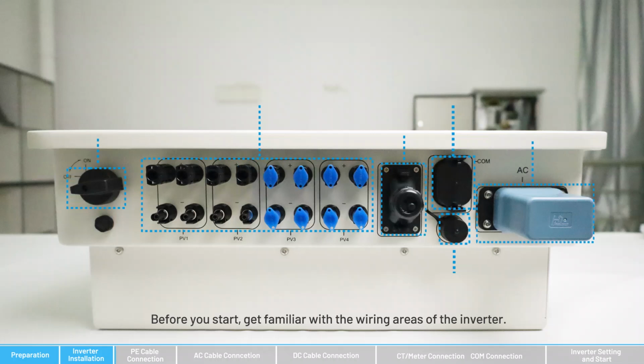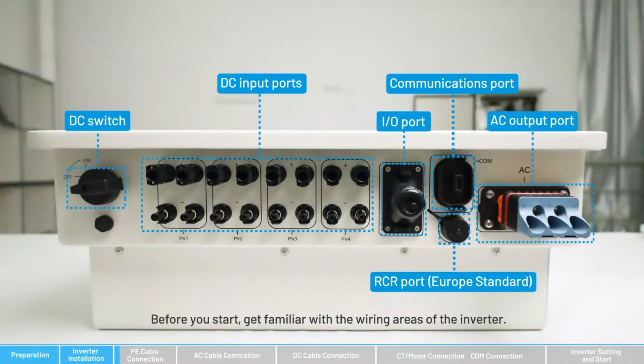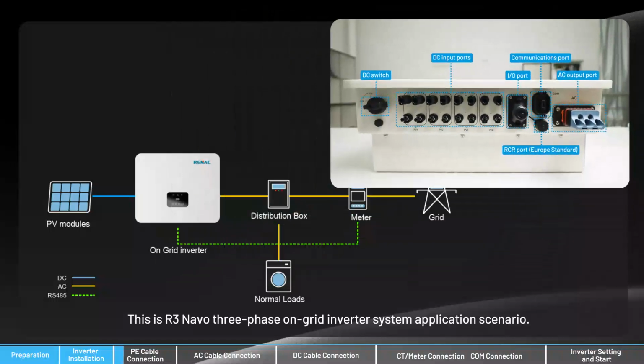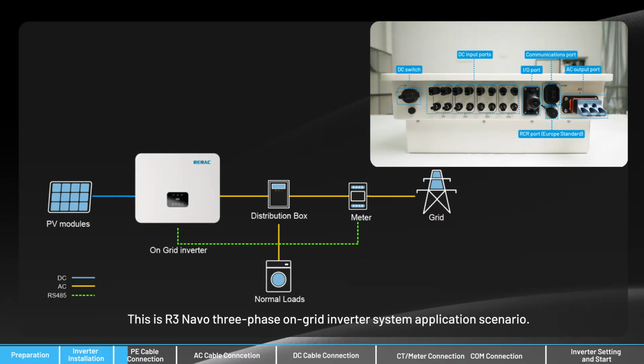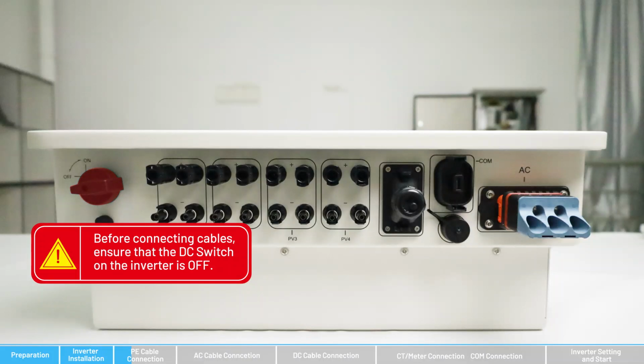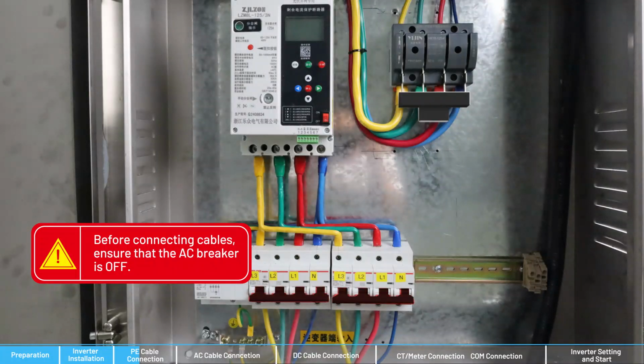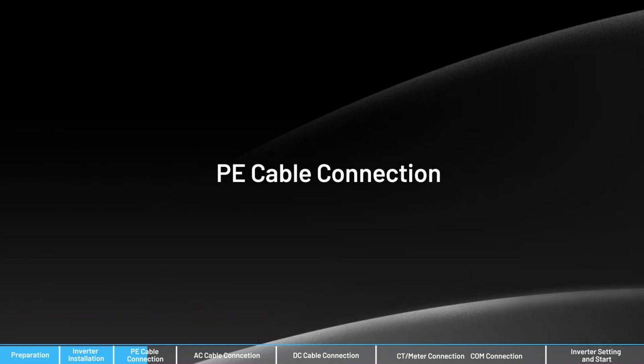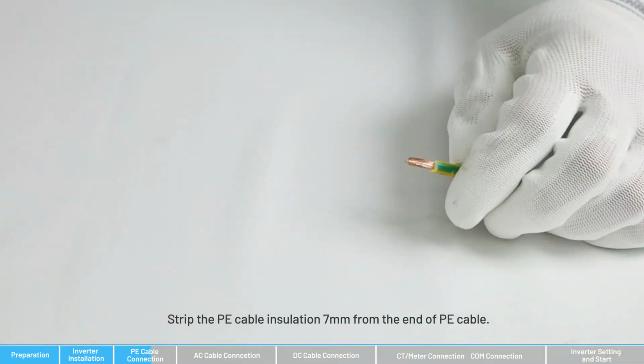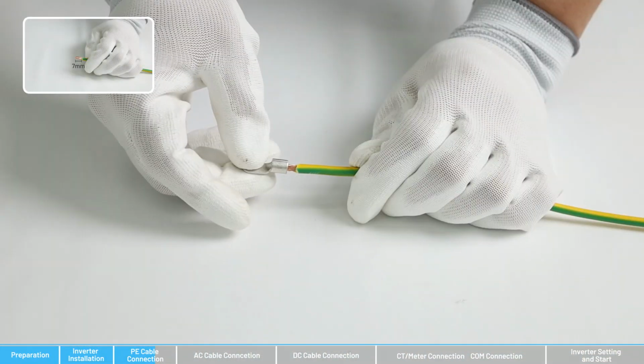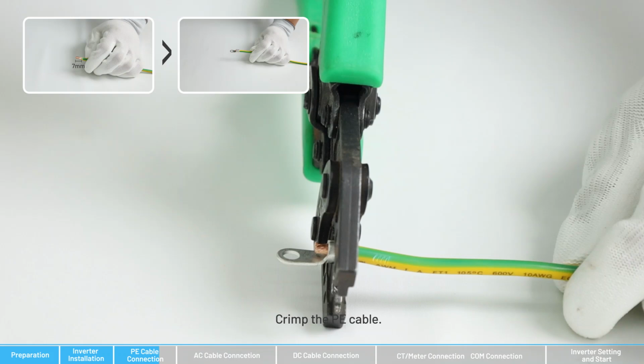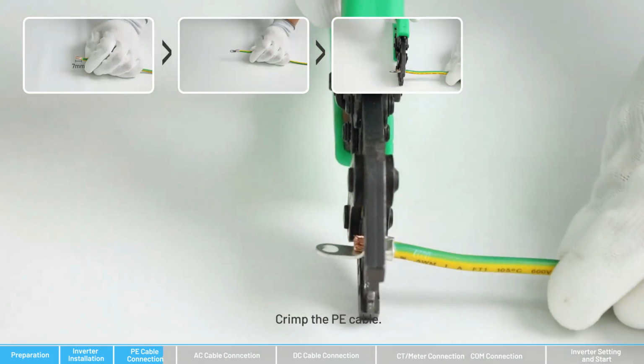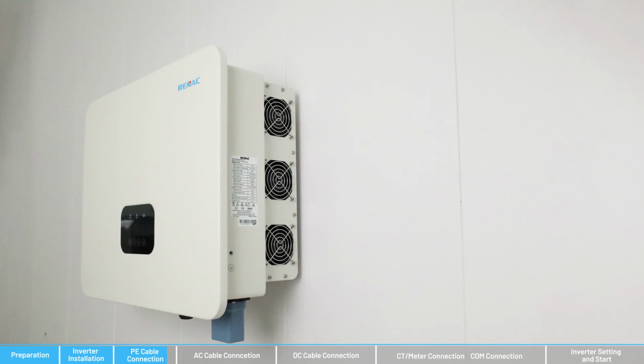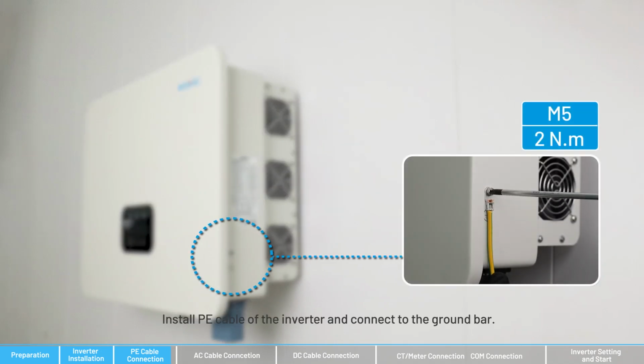Before you start, get familiar with the wiring areas of the inverter. This is our R3 Navo 3-phase on-grid inverter system application scenario. Strip the PE cable insulation 7 mm from the end of the PE cable. Crimp the PE cable. Install the PE cable of the inverter and connect it to the ground bar.